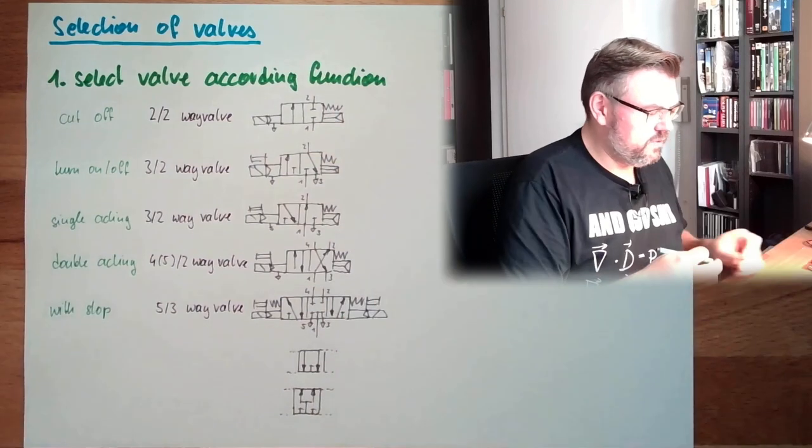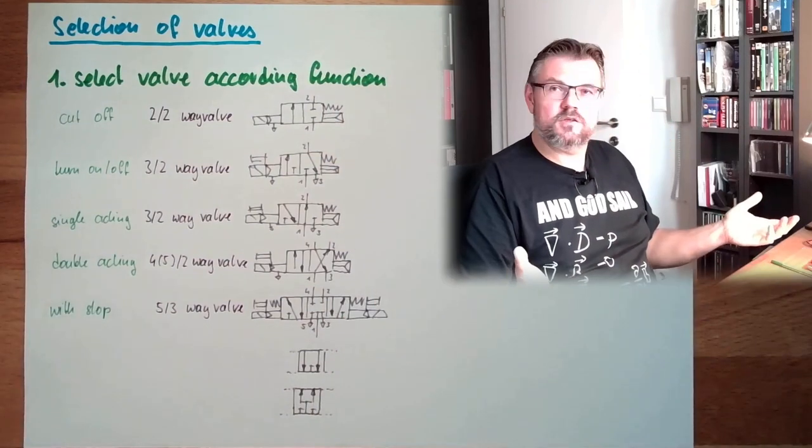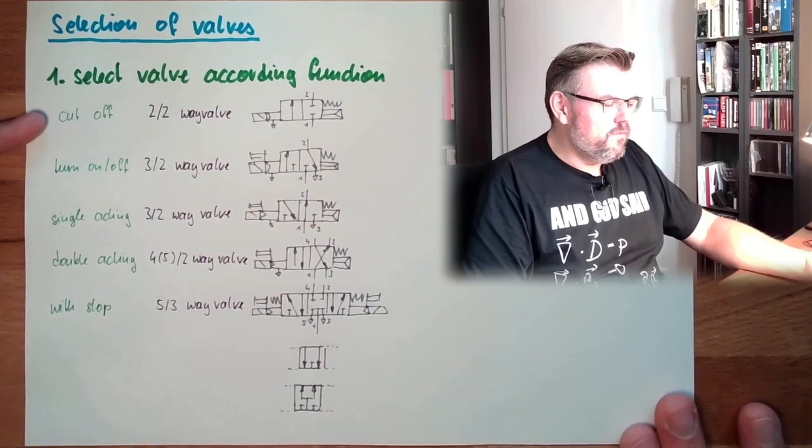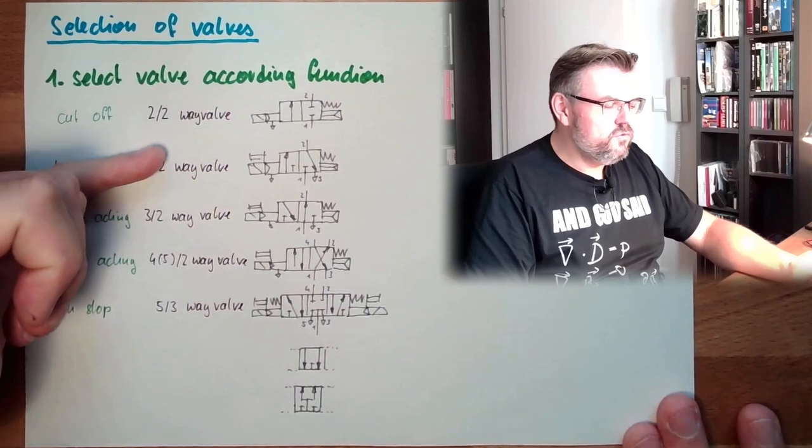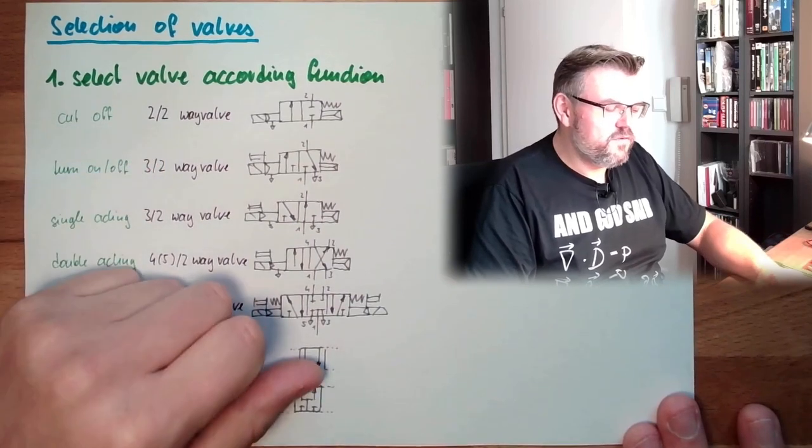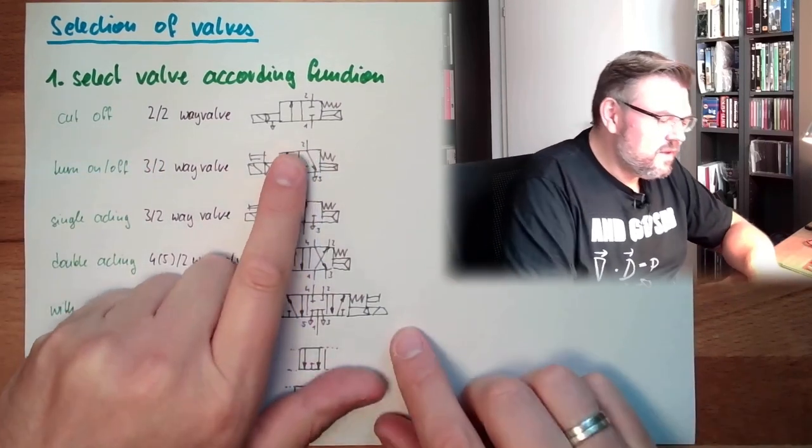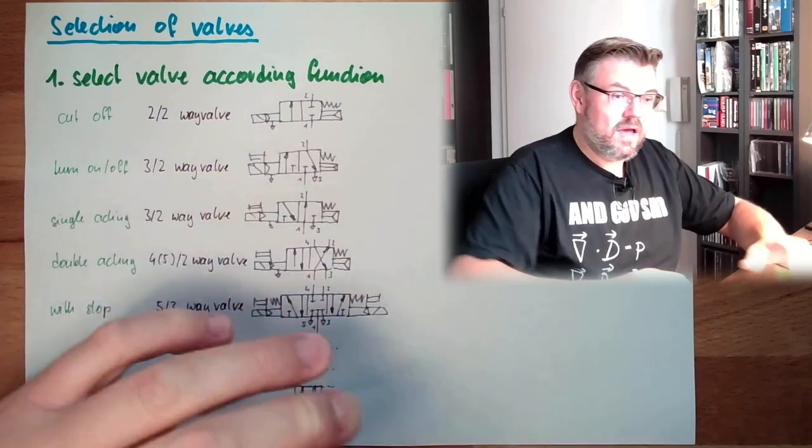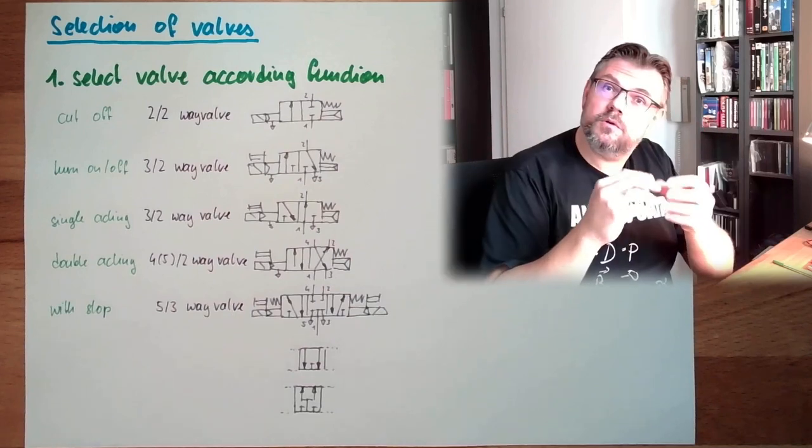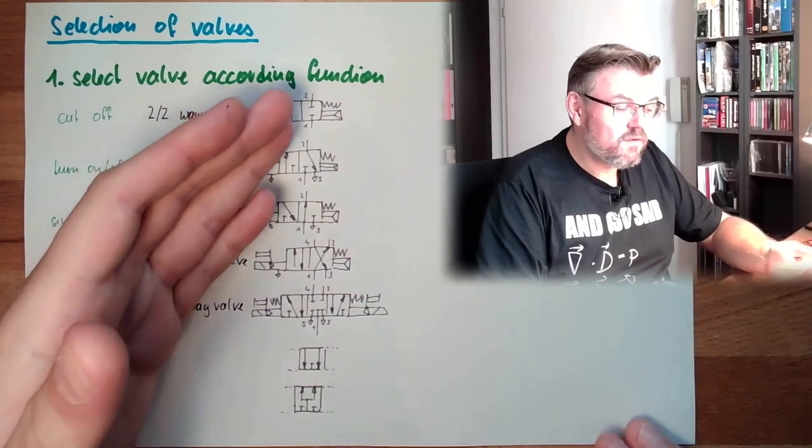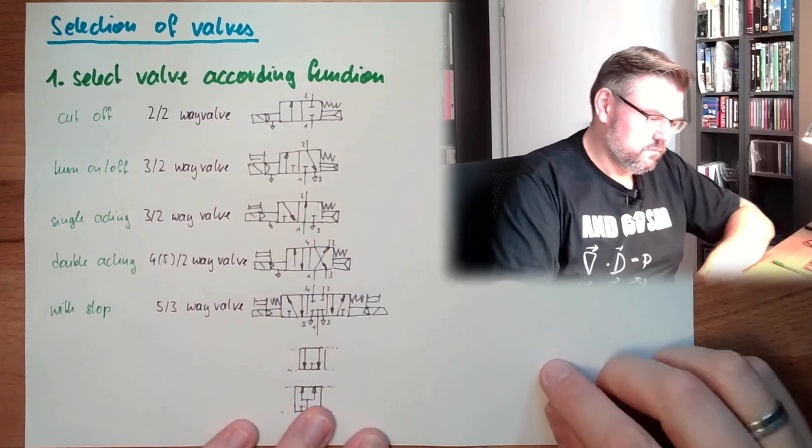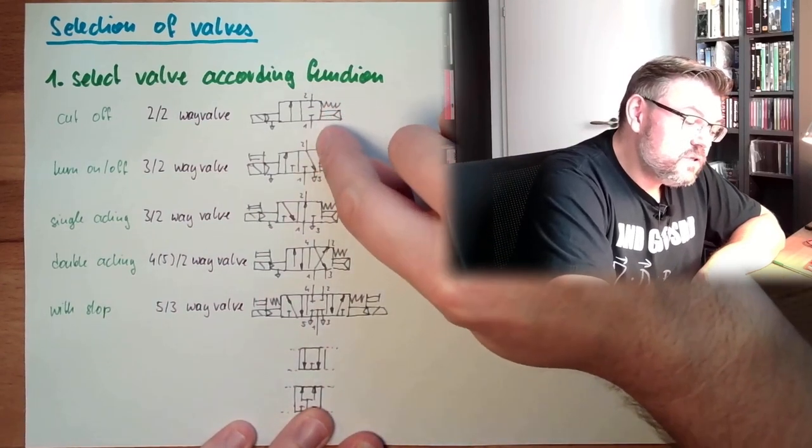I have already put here some possible functions. If you want to just cut off the stream, then a 2/2 way valve would be sufficient. And here we see, we said usually these valves are pre-controlled, so that we don't have a coil which is that big. We have a tiny coil switching a tiny valve, this tiny valve is switching the big valve. So this is spring loaded here, rest position locked, turn on, flow.